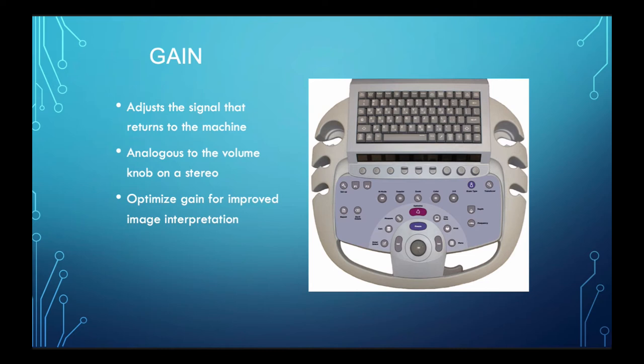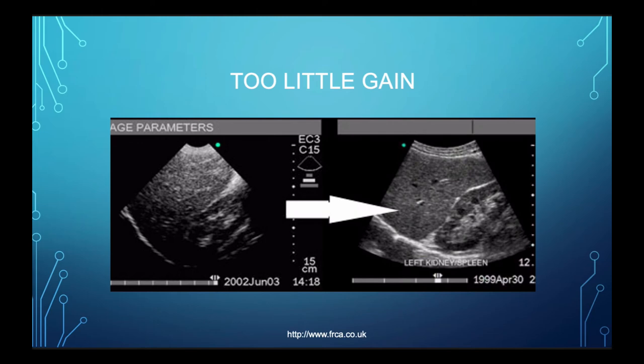Gain — we can think of this as the attempt to overcome attenuation through increasing the gain. This is basically amplifying the signal through post-processing in the computer of the ultrasound, and it can help make the image more visible on the screen. We have to remember that gain increases both signal and noise — it doesn't always make for a better image. It just makes it easier to visualize; it makes it brighter on your screen. Here's an example of an image with too little gain — we have the diaphragm-liver-kidney interface, but on the left, in the far field, you can't really make out the structures. By increasing the gain on the same structures on the right, you can definitely make out the structures better and visualize them better on the screen.